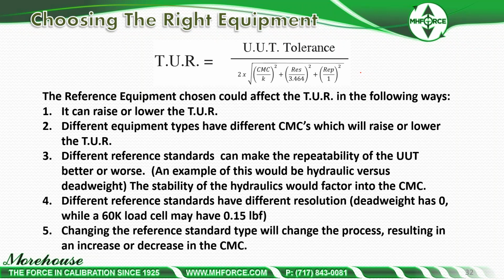Different reference standards can make the repeatability uncertainty better or worse. So the goal is to have a reference standard that's plumb, level, square, rigid, and has low torsion. Any of those things that aren't in line are going to make it worse. Also, hydraulic versus dead weight. On hydraulic, you're going to have creep. On dead weight, you're just going to have that load there, and you're going to have creep on the scale. But the stability of hydraulics would factor into the CMC uncertainty parameter.